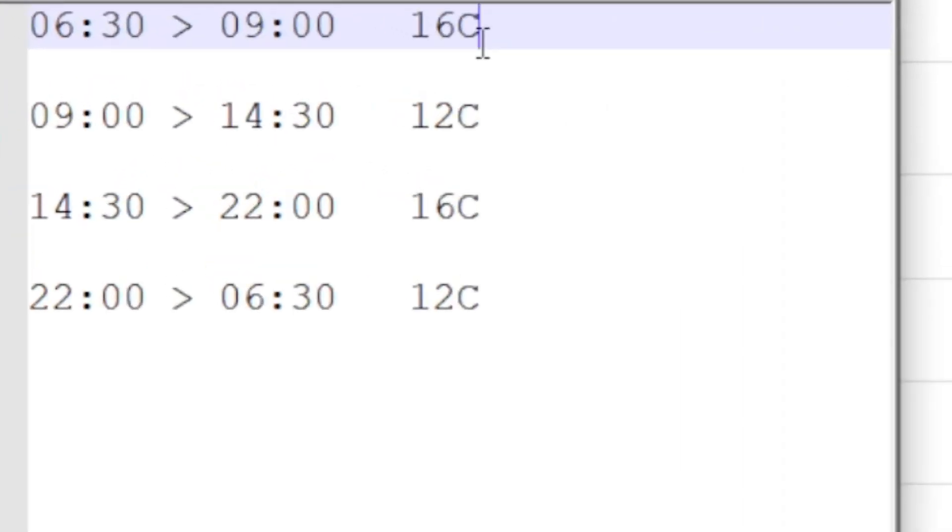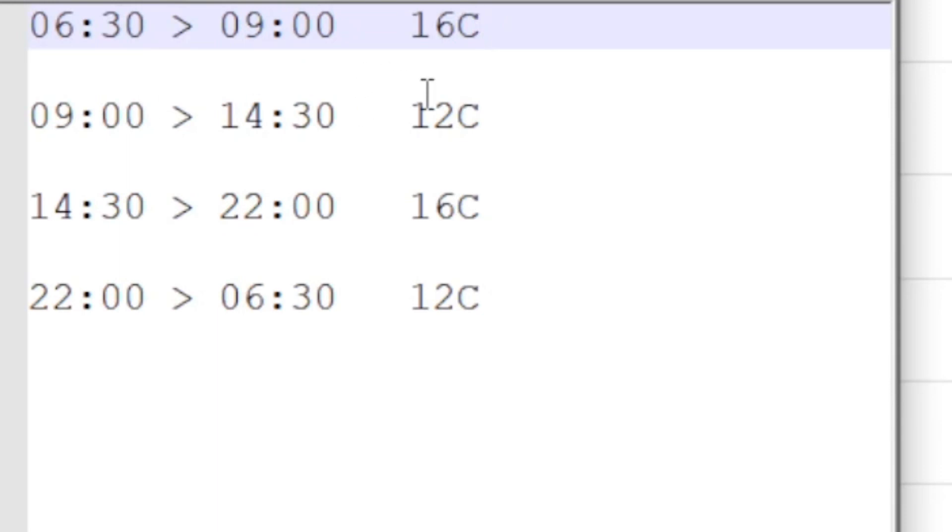So I want to hit around 16 degrees. So what I'm doing is I've got some automation set up, so that every five minutes I'm checking the temperature sensor, and I'm saying that hey, if it's above 16 degrees, turn the heaters off. If it's below 15 degrees, then turn the heaters on. So just trying to keep it between 15 and 16 degrees. And it's the same logic for the rest of the day. So during the day, cool things down a little, then in the afternoon and evening, warm things up again, and then overnight cool it down.